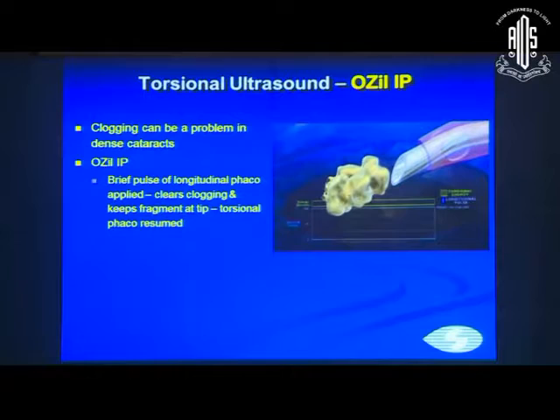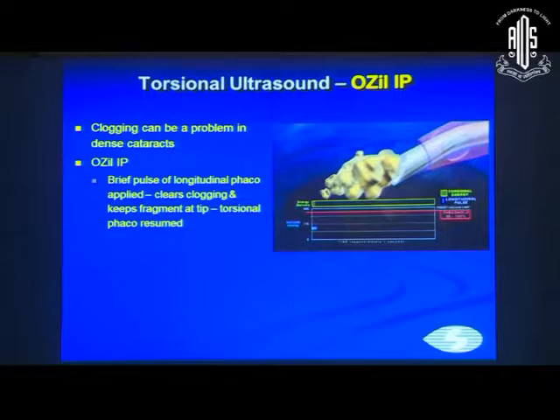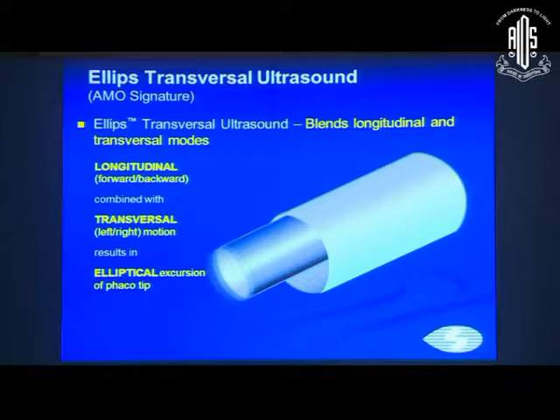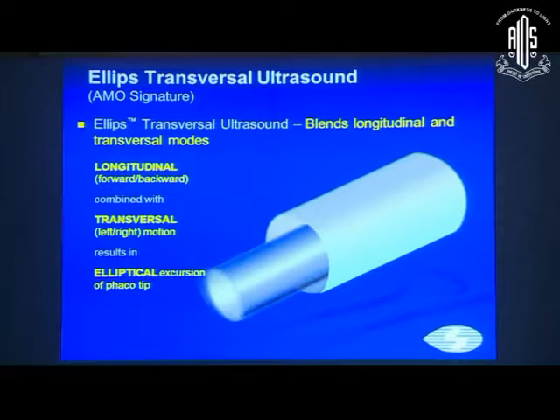Clogging was a problem with torsional ultrasound, and this has been solved with OZil IP, which gives pre-pulses of longitudinal ultrasound, clears the clogging, and keeps the fragment on the tip, after which torsional phaco is resumed. Elliptical ultrasound blends longitudinal and transverse ultrasound: the forward-backward longitudinal movement combined with left-to-right transversal motion results in an elliptical excursion of the phaco tip.